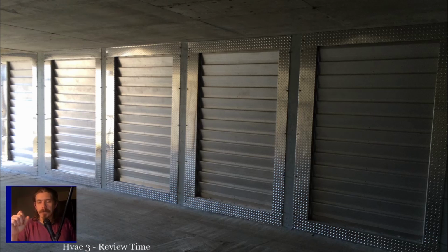Okay. So in general, if you're going to have separate fan speeds, what you would do is end up going into a fan relay, like, if you've got any safeties on it, and then you'll go into another normally closed, normally open relay that'll energize only one speed at a time. Because a double pole relay isn't going to get stuck in both positions. I've never seen a situation where that mechanical relay can get stuck in the normally closed and normally open positions. If it's got an off position, it can get stuck there, but it doesn't get caught with both contacts energized at the same time. It's almost impossible unless there's some heavy damage to that relay. So, in general, if you've got multiple speeds on a unit, you want to control those by a single relay so that only one speed can get energized at any given time.